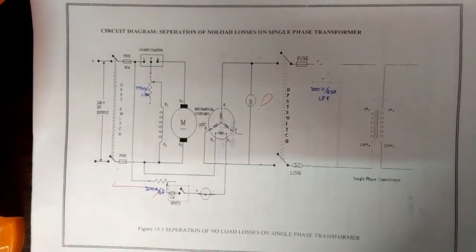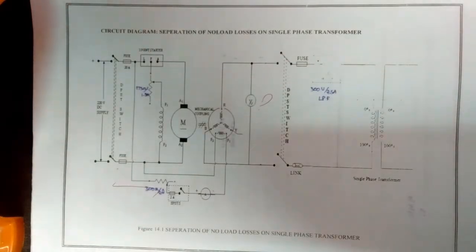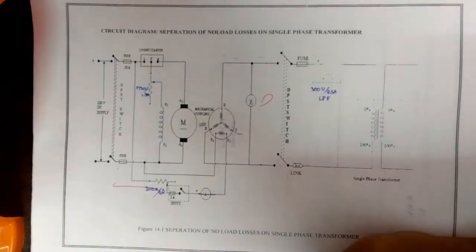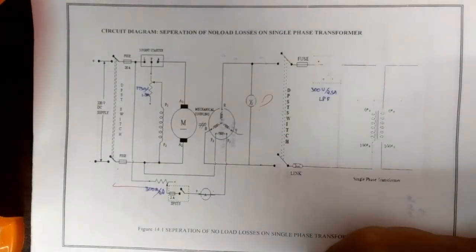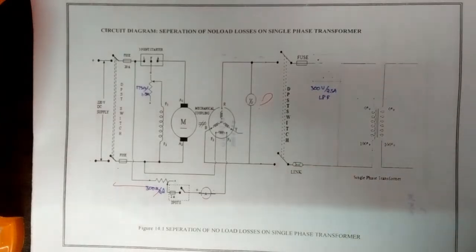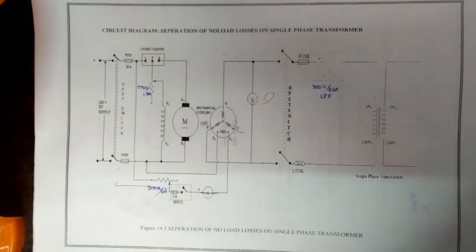Before we move to the procedure, the precautions we should take care is that the motor field rheostat is kept at the minimum resistance position. The alternator field rheostat should be kept at the maximum resistance position.